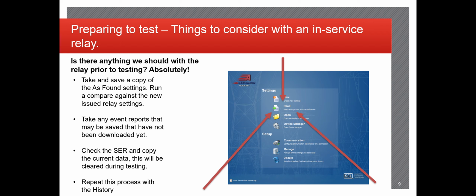This is also really beneficial when you're doing your testing. If something doesn't line up correctly during your testing procedures, you could possibly look back at the relay logic that was found in the relay to see if anything may line up or differ depending on what you're testing. You also want to run a compare against the new issued relay settings to provide to the client, to show them, hey, this is what we found, this is what you gave us, and these are the only differences that are going to be issued.